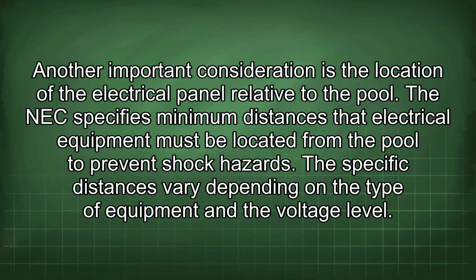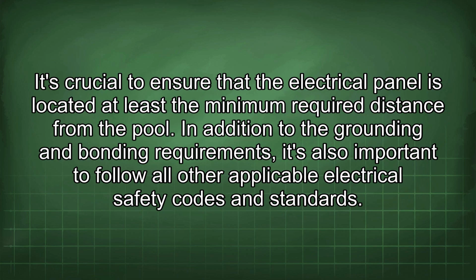Another important consideration is the location of the electrical panel relative to the pool. The NEC specifies minimum distances that electrical equipment must be located from the pool to prevent shock hazard. The specific distances vary depending on the type of equipment and the voltage level. It's crucial to ensure that the electrical panel is located at least the minimum required distance from the pool.